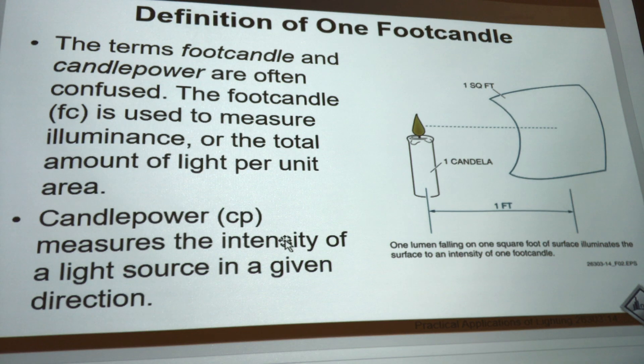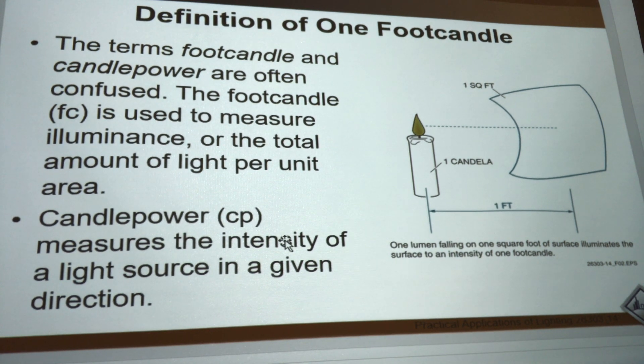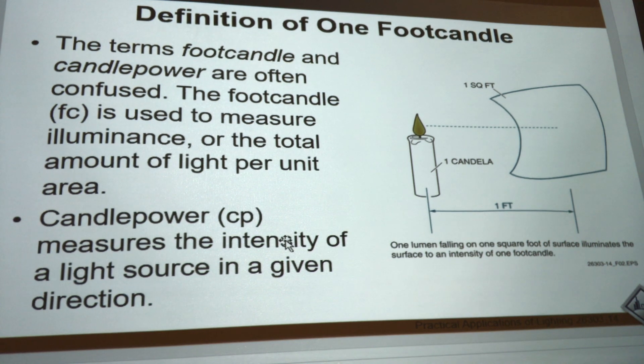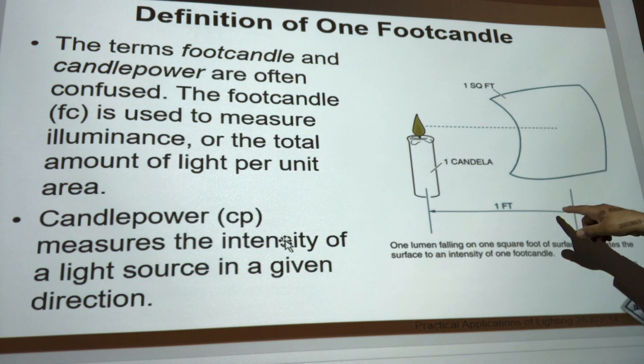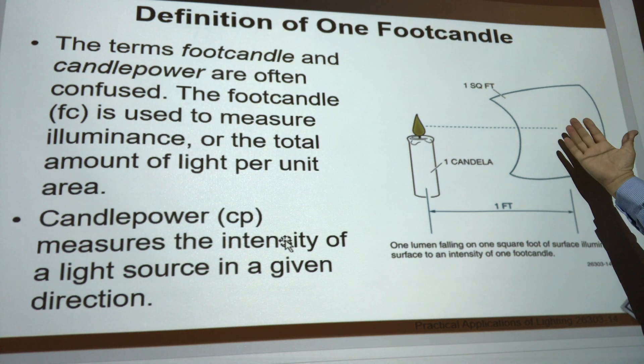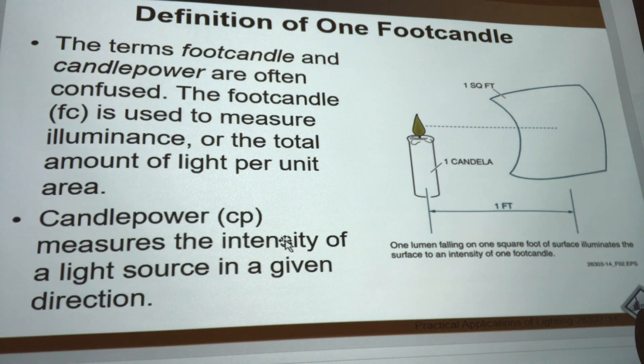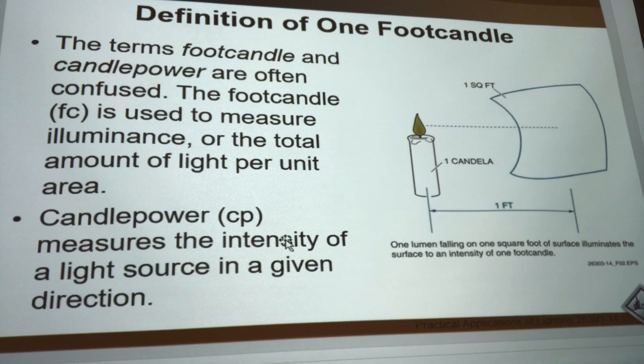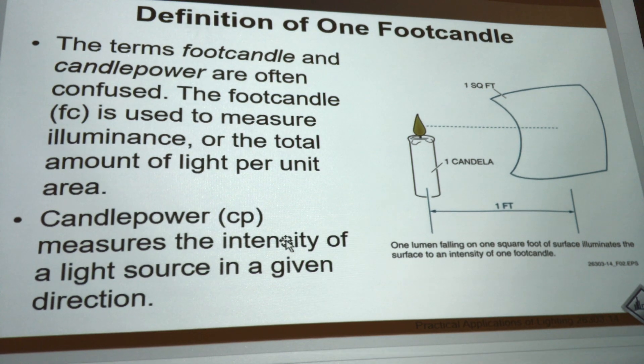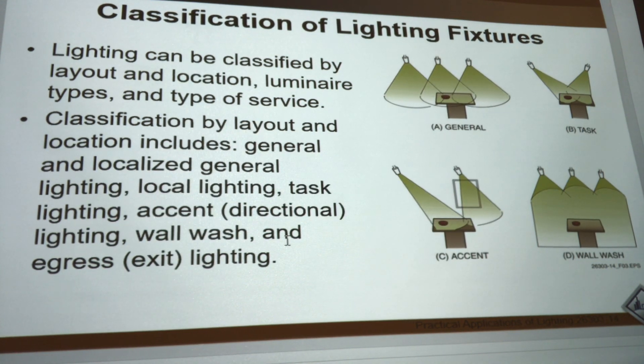Here's the definition of foot candle. The term foot candle and candle power are often confused. A foot candle (FC) is used to measure illuminance, or the total amount of light per unit area. One square foot, one foot away — that's how much light we get on a desktop. That's foot candles, and it's really important when we work in an office, studio, or operating room — we have to have a certain amount of foot candles on our subjects.